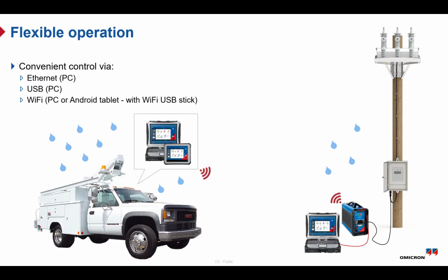The ARCO 400 offers multiple ways to control the device depending on your preference and the testing situation. You can connect using Ethernet, which is commonly used for stable communication with a PC. There is also a USB option, which is simple for quick and direct connection. And for more flexibility, you can use Wi-Fi. With the Wi-Fi USB adapter, which is called the EDIMAX, you can control the device wirelessly from a PC or even Android devices like phones or tablets. This is especially useful in the field where you may want to operate the test set from a distance, for example, from inside a vehicle or a safer location.